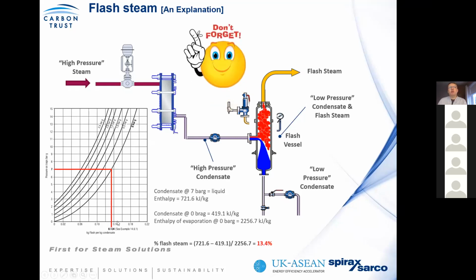And it's important not to forget that this is unavoidable. So with any high pressure application which reduces high pressure condensate to low pressure condensate through a 0 pressure condensate recovery system, you're going to create flash steam, and it is unavoidable.